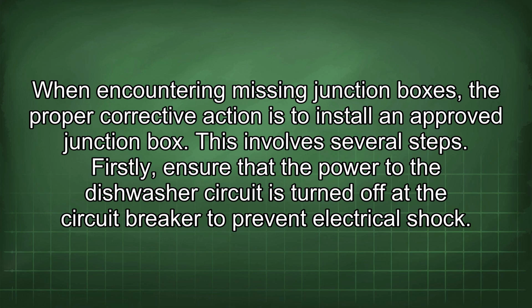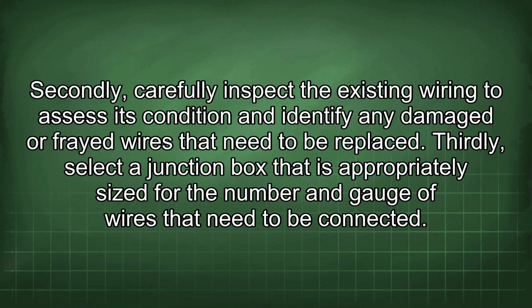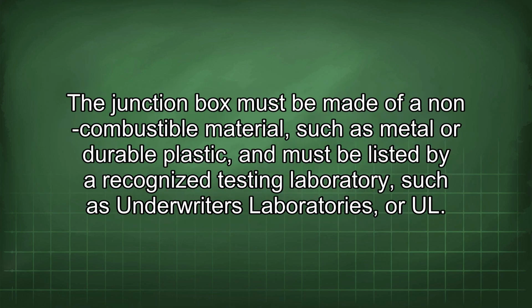This involves several steps. Firstly, ensure that the power to the dishwasher circuit is turned off at the circuit breaker to prevent electrical shock. Secondly, carefully inspect the existing wiring to assess its condition and identify any damaged or frayed wires that need to be replaced. Thirdly, select a junction box that is appropriately sized for the number and gauge of wires that need to be connected. The junction box must be made of a non-combustible material such as metal or durable plastic, and must be listed by a recognized testing laboratory such as Underwriters Laboratories or UL.